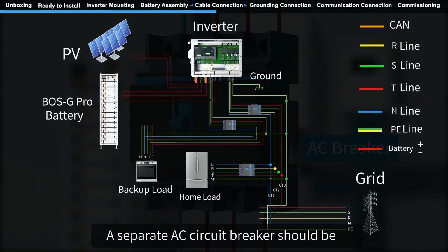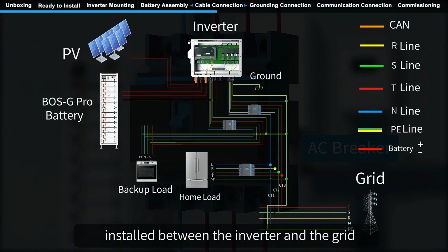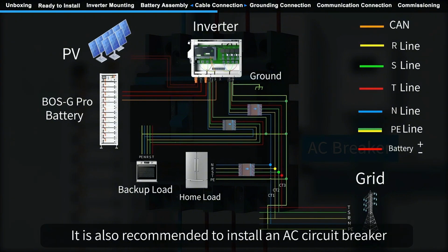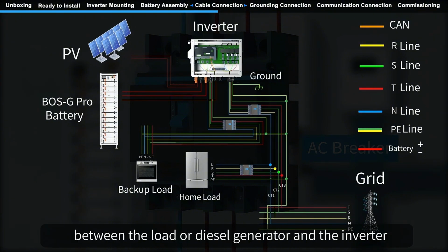A separate AC circuit breaker should be installed between the inverter and the grid. It is also recommended to install an AC circuit breaker between the load or diesel generator and the inverter.